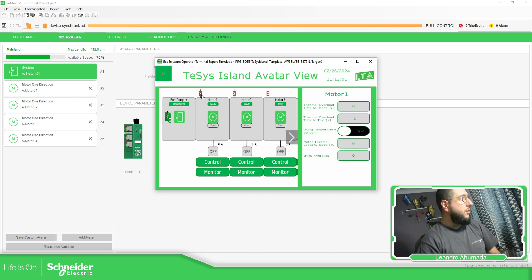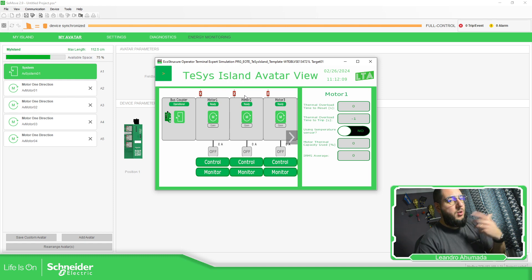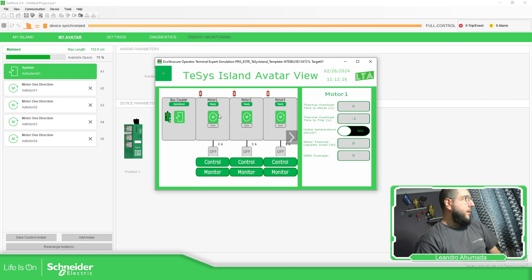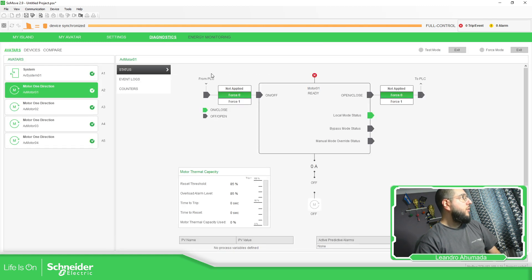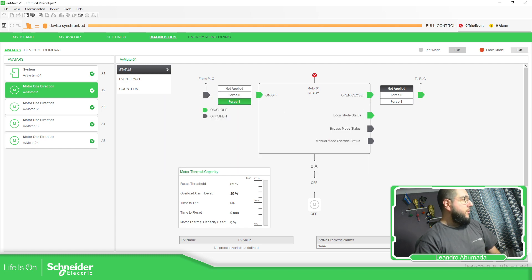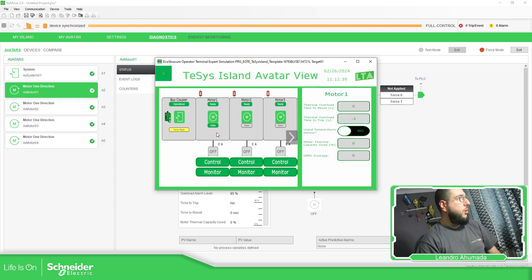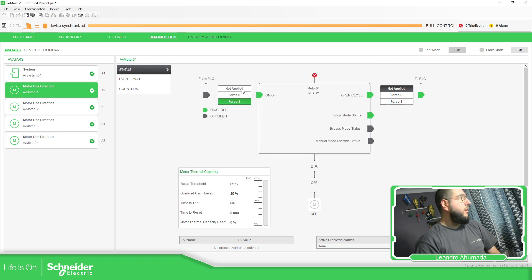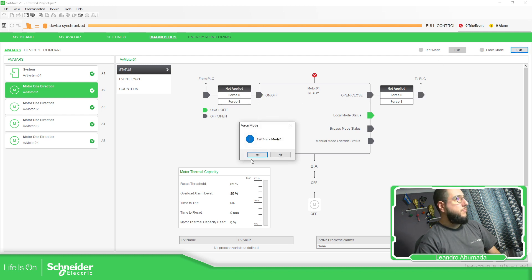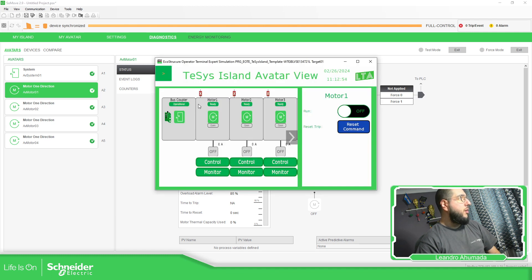In my case the temperature sensor is not configured. You can see there is no voltage above — here I can see the feedback from the motor circuit breaker, and even if the contactor is closed, there is nothing above. We can also see the status of the bus coupler. I'm going to force this to one — force. And if we go here, you can see it is closed but in force mode. If we exit force mode, you can see the island is no longer in force mode.